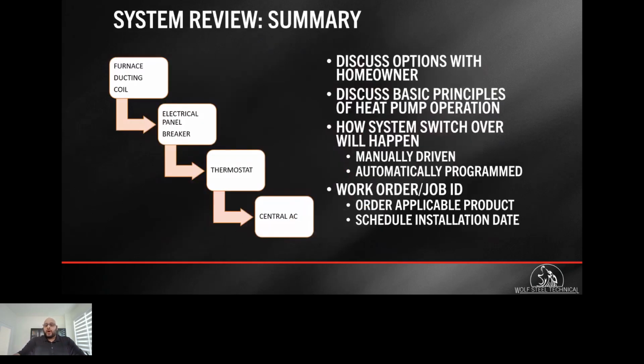We want to review the options with the customer and educate them as best as we can, to make sure that they can make an informed decision. Explain the basic principles of heat pump operation and how the system switchover happens. There are a lot of misconceptions with customers, thinking that just because they got a heat pump means that they're never going to use their secondary heat. Well, that's not true. Then once everything is set in order, order your equipment and set a date for the installation.